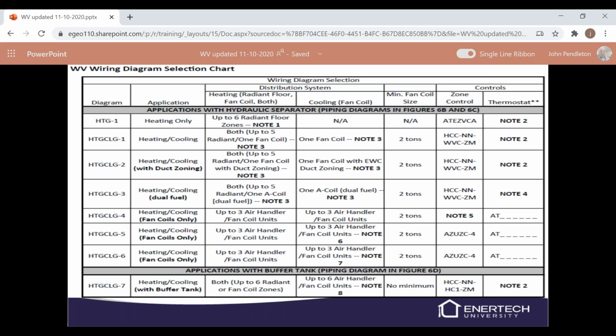In the IOM, it will list this wiring diagram selection chart. So you can look in here and see if you have a heating and cooling dual fuel, that you would use the HTG CLG-3 diagram. And that diagram number, as you scroll down the IOM, it'll bring up these wiring diagrams. So you can see if we've got a heating and cooling dual fuel, which is right there in the middle of the screen, it'll be able to do up to 5 radiant and 1 A coil, which is a dual fuel zone. And it'll have 1 A coil, so you can do heating and cooling with it. Minimum tonnage is 2 tons, and it'll tell you the zone control. And then it'll list some notes on different types of thermostats you can use.